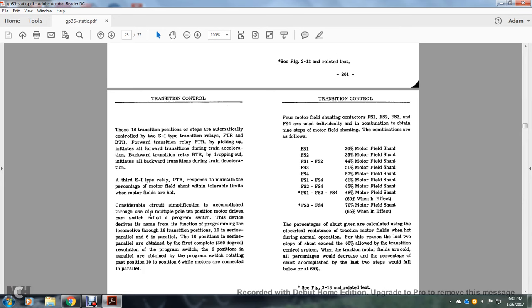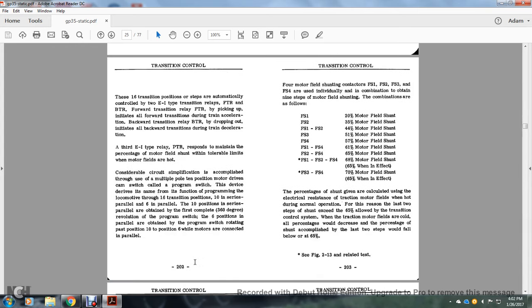Considering the circuit simplification accomplished through the multiple pole, 10 position motor driven cam switch of the program switch, the device is named for its function of programming the locomotive through 16 transition positions: 10 series parallel and 6 parallel. The 10 position series parallel are obtained with the first complete 360-degree revolution of the program switch. The 6 position parallel are obtained with the program switch rotating past position 10 to position 6, while the motors are connected in parallel circuit.